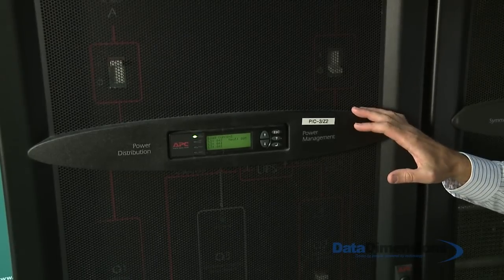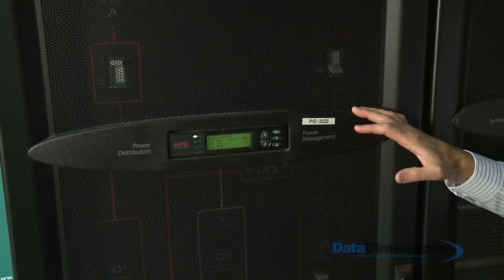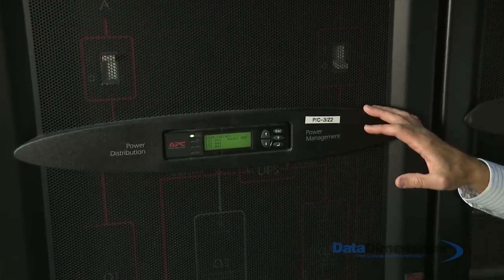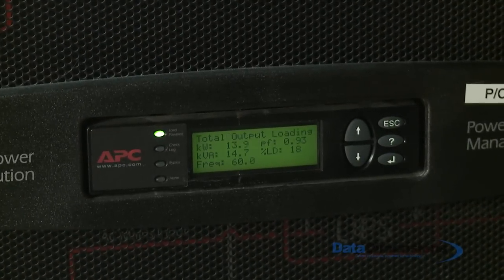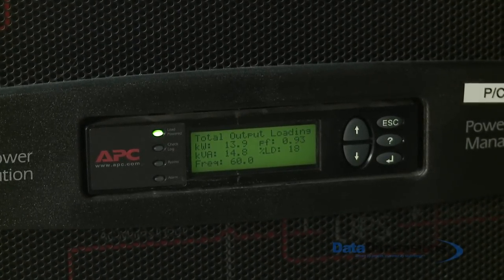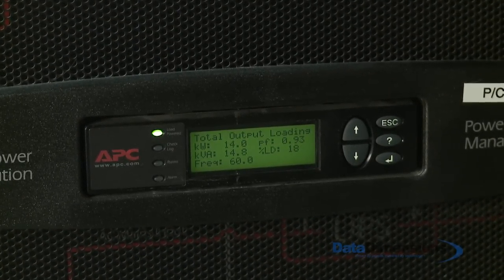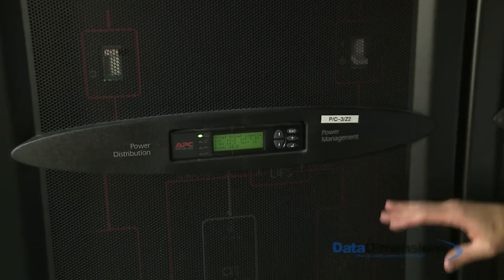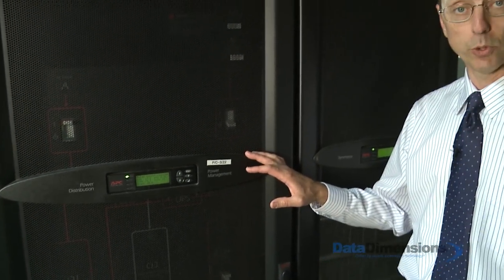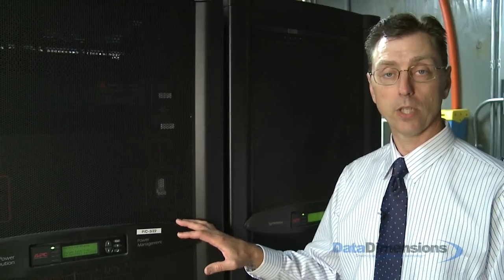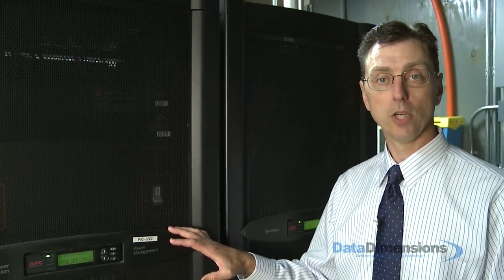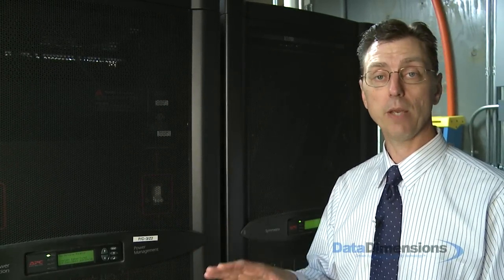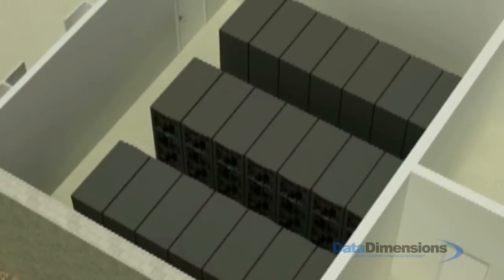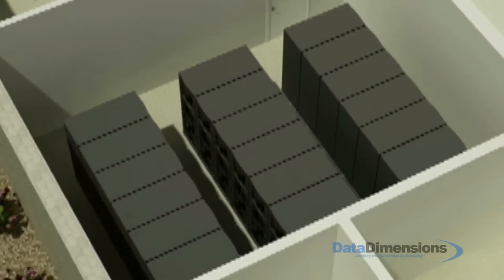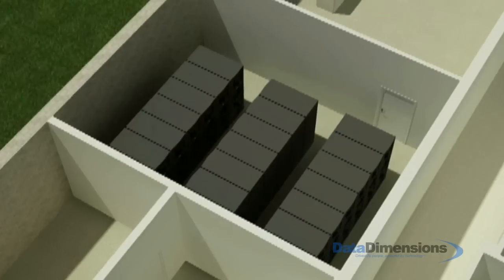For power systems in the data center, we use APC infrastructure. This 80 kilowatt UPS unit is constructed of N+1 architecture. Any single component failure does not cause a disruption in service. This unit is located in the electrical room. It supplies power to the left half of every single rack. We have a redundant system in the same N+1 architecture inside the data center, providing power to the right hand of every rack.